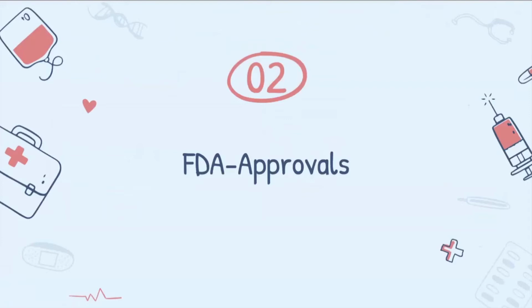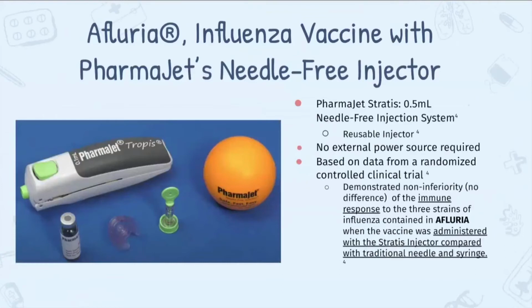Next, I'll be going into the FDA approvals of jet injectors. Looking at the FDA approval for jet injectors, the FDA approved Afluria influenza vaccine with PharmaJet's needle-free injector. PharmaJet's needle-free injector is called PharmaJet Stratis 0.5 milliliter needle-free injection system, which consists of a reusable injector that delivers a single dose with a disposable cartridge. No external power source is required. The device contains an adapter that can be used with vaccine vials.